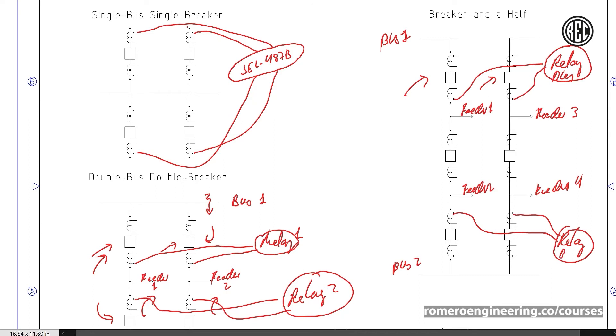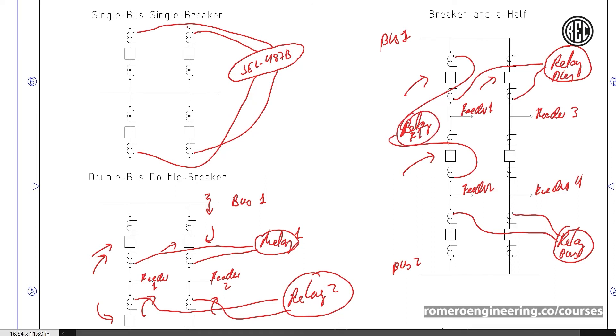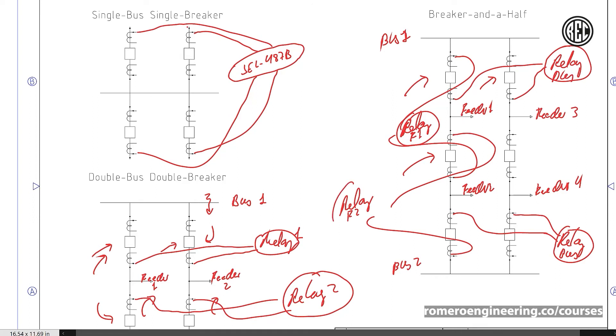The middle breaker is shared between the protection of feeder one and feeder two. Feeder one uses the CT on its outer breaker and the middle CT, feeding relay F1. Feeder two uses the middle CT and its outer CT, feeding relay F2. If there's a fault on feeder one, we trip the outer breaker for feeder one and the middle breaker. If there's a fault on feeder two, we still trip the middle breaker and feeder two's outer breaker. That's why it's called a breaker and a half — each feeder effectively has one full breaker and shares half of the middle breaker.